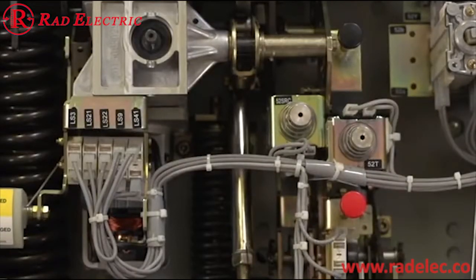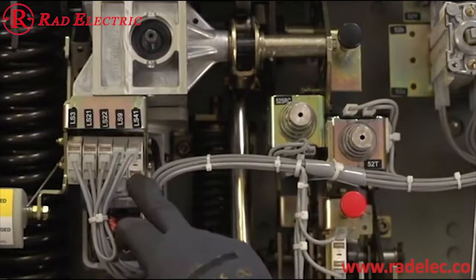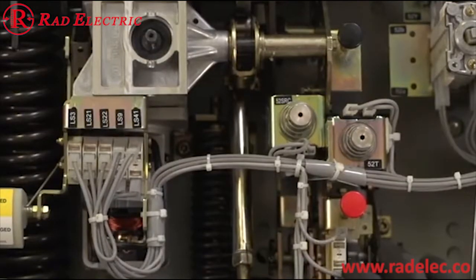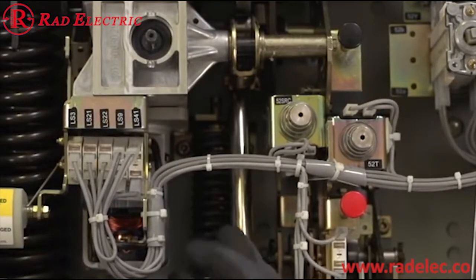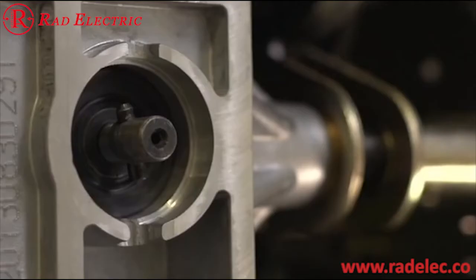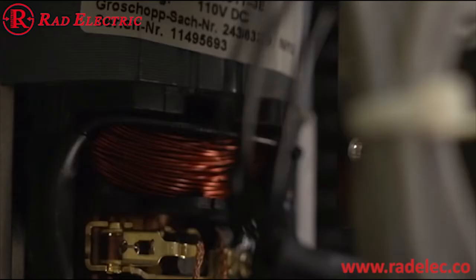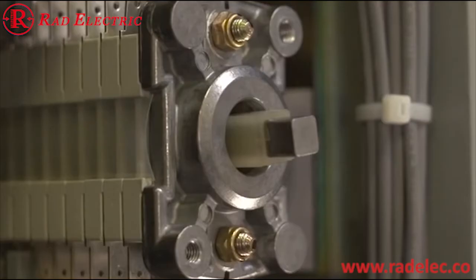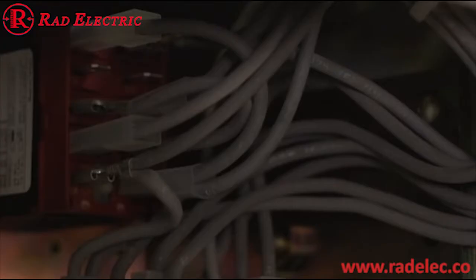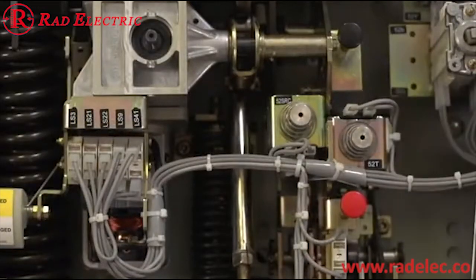There are several limit switches that are internal parts to the circuit breaker control circuit. This electric charging motor connects to the main drive gearbox, which can be operated mechanically or electrically. These are the auxiliary switches, and this is the anti-pump or Y relay. This is the wiring harness which goes to the 16-pole disconnect.